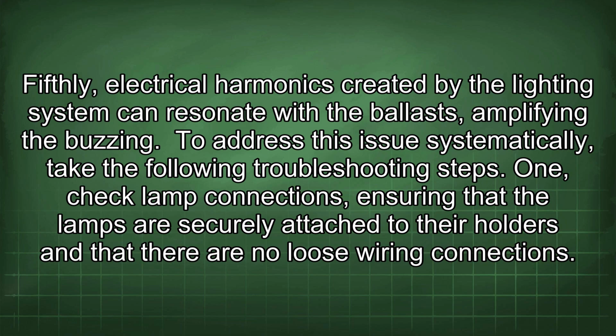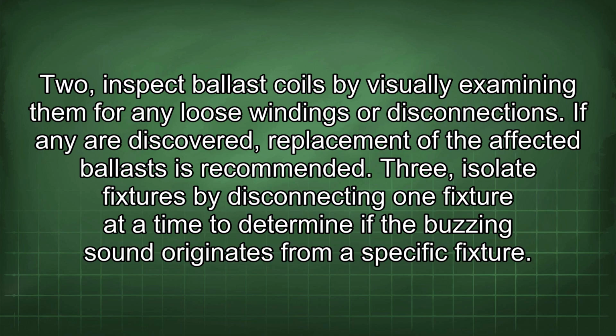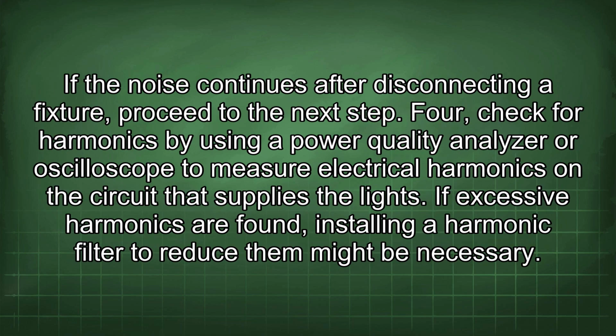To address this issue systematically, take the following troubleshooting steps. 1. Check lamp connections, ensuring that the lamps are securely attached to their holders and that there are no loose wiring connections. 2. Inspect ballast coils by visually examining them for any loose windings or disconnections. If any are discovered, replacement of the affected ballasts is recommended. 3. Isolate fixtures by disconnecting one fixture at a time to determine if the buzzing sound originates from a specific fixture. If the noise continues after disconnecting a fixture, proceed to the next step.